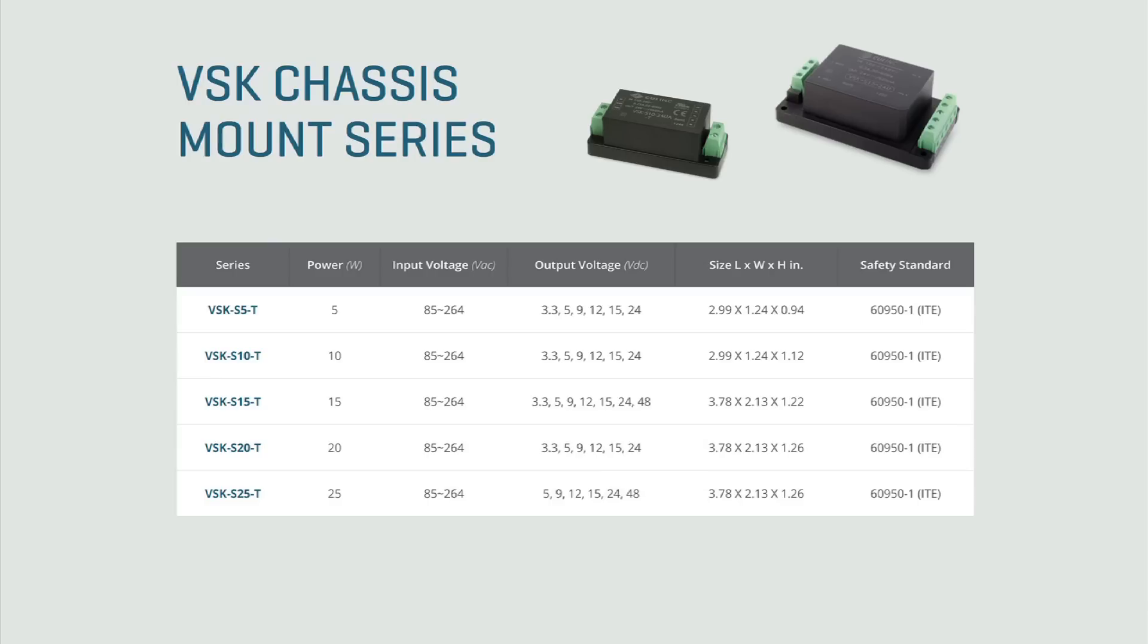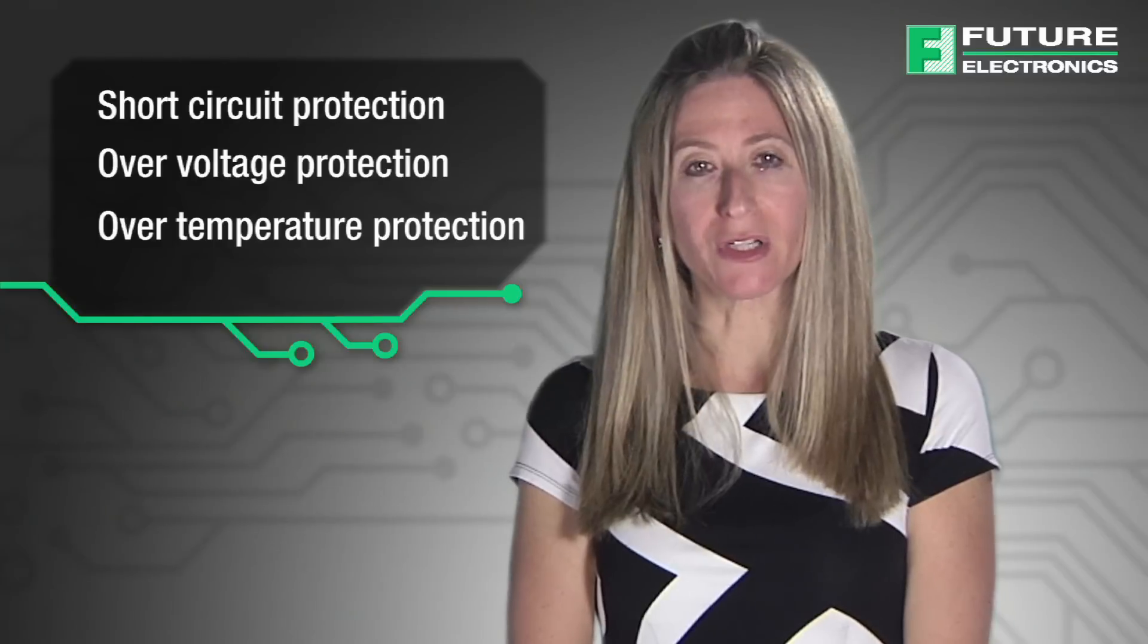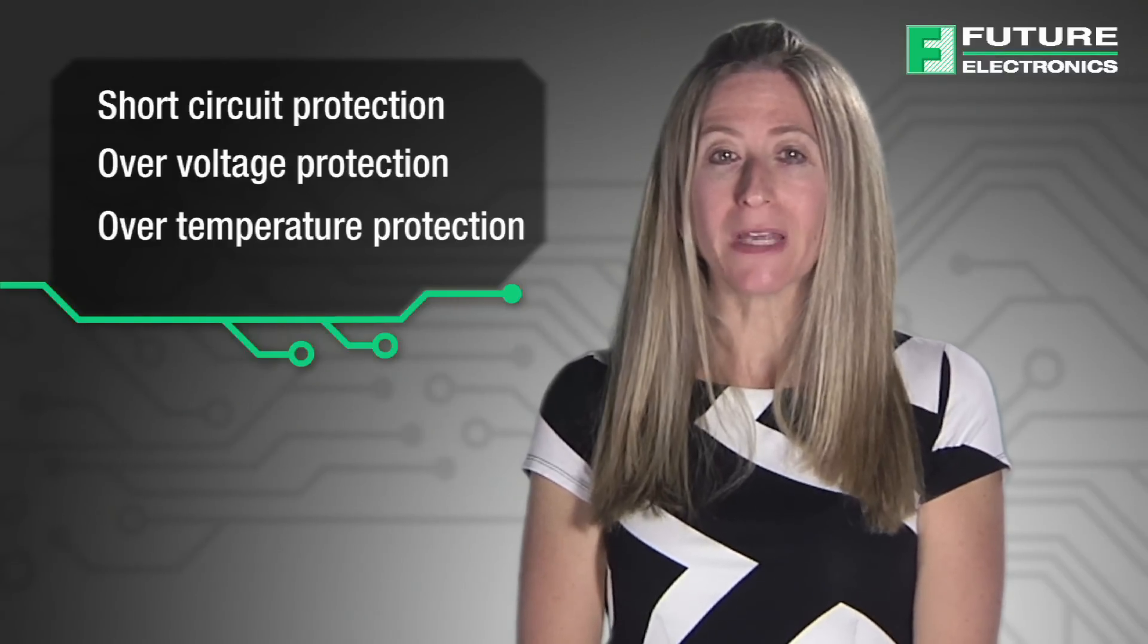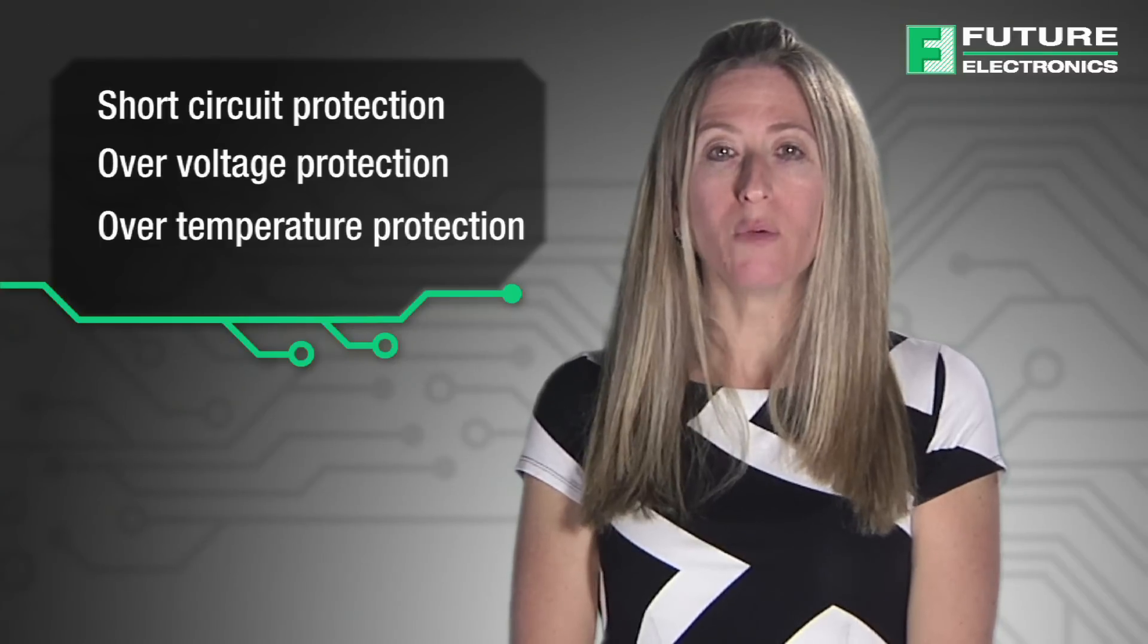The VSK-T series is offered in configurations ranging from 5W to 25W. The VSK series comes with built-in short circuit, over-voltage, and over-temperature protections. In the event of a fault in any of these areas, the converter's output will shut down, recovering automatically when the fault is removed.